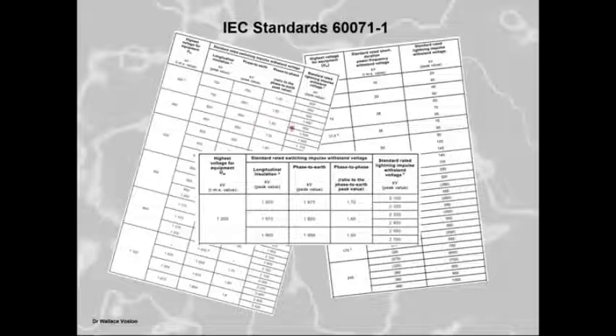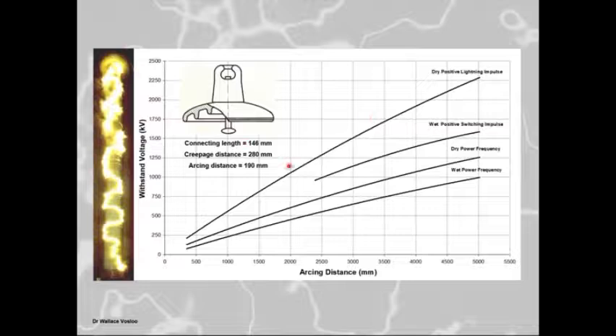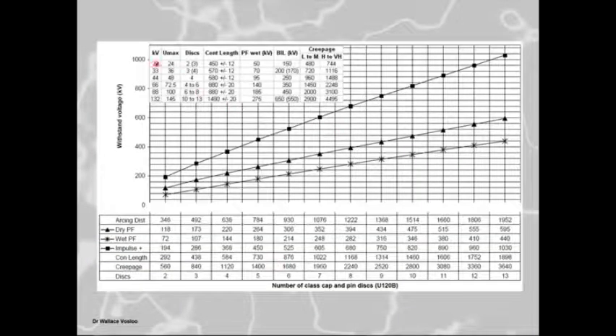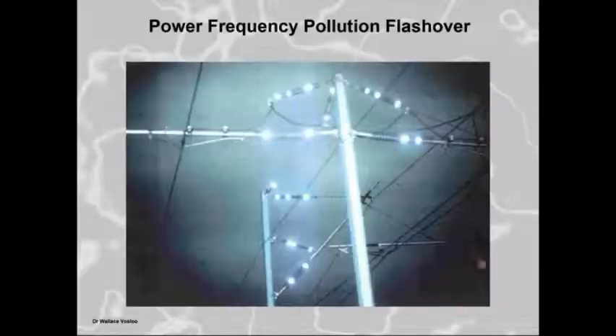And here are the curves for a standard glass disc for wet power frequency, dry power frequency, wet switching impulse, and dry lightning impulse. So you can see, this is just to give you an idea of when the actual wet switching starts playing a role. And here it is for lower voltage levels, from 22 to 132, getting an idea of your Umax and so on. This is just a little design chart you can feel free to use when you're working with glass discs.